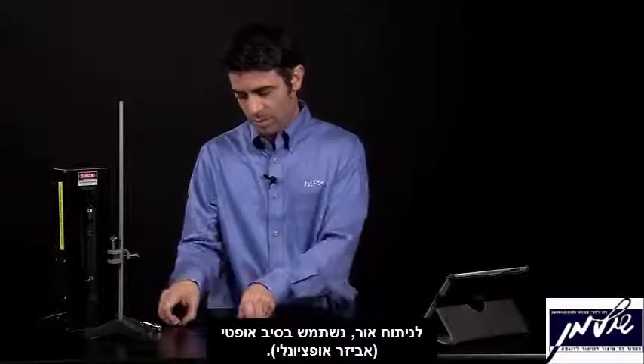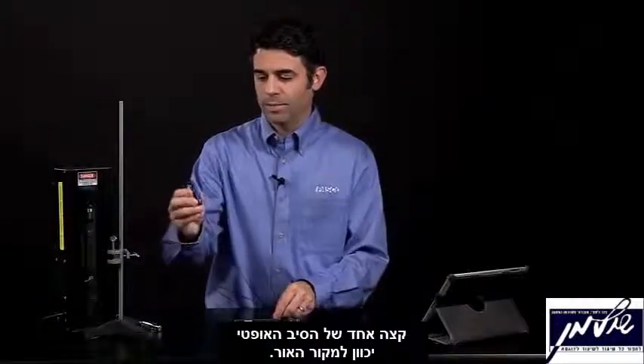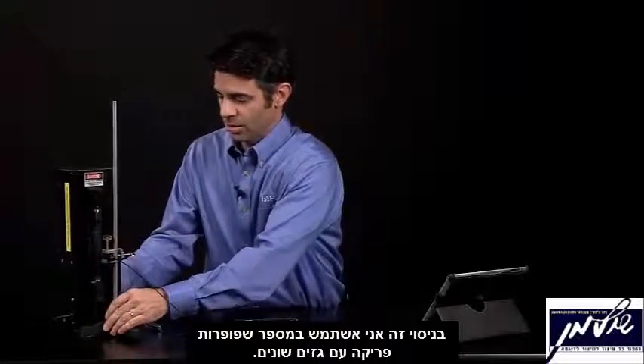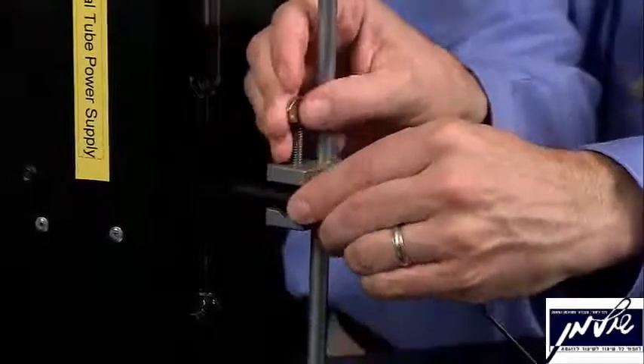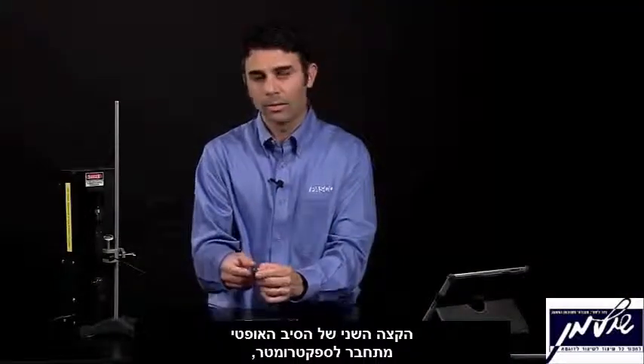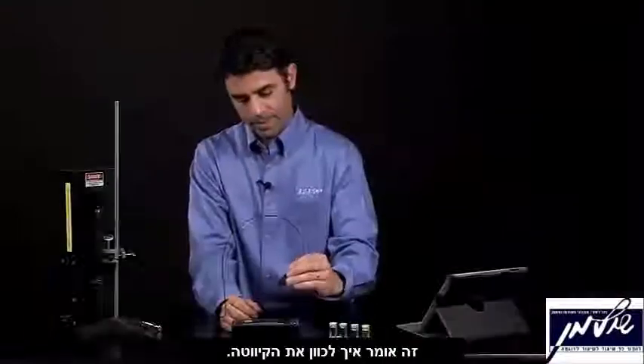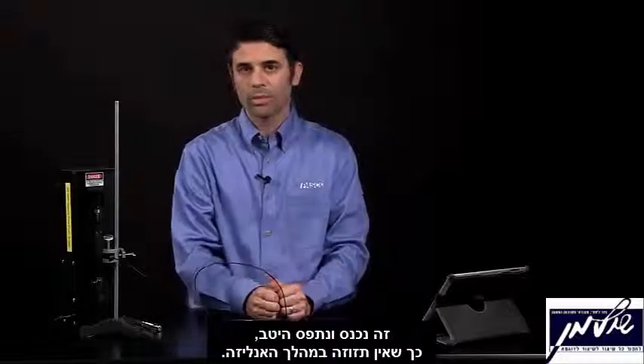To analyze lights, we're going to use the optional fiber optic accessory. One end of the fiber optic accessory you point at a light source — in this case, some gas emission discharge tubes — and use a clamp to hold it steady. The other end goes into the spectrometer, with the arrows pointing towards the detector. It's a very snug fit so that it doesn't wobble around during analysis.